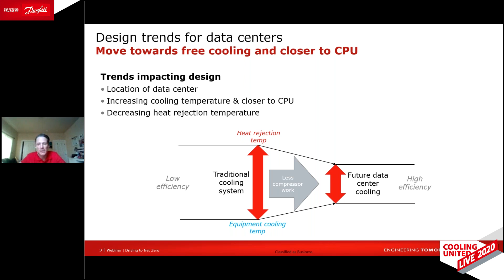For cooling temperature, as the market has come to realize that you're not cooling people here, you're cooling the equipment, that means you can go to a higher temperature and also get closer to that heat-generating equipment. This significantly impacts the design and operating temperatures, along with decreasing the heat rejection temperature through a combination of solutions.